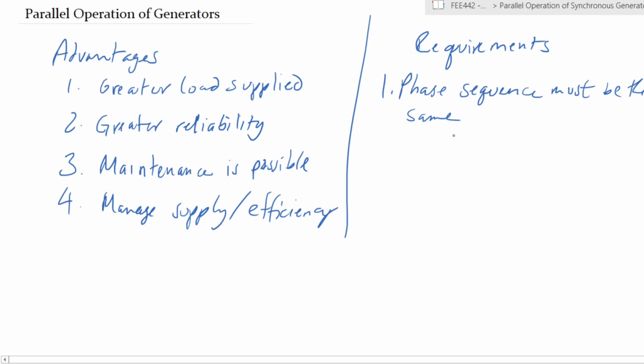Phase sequence means the order in which the red, yellow, and blue phases reach their peaks must be the same for the system that you're connecting to and for the generator that you wish to connect to that system. They must be running in the same order. So if your system that you're connecting to is red, yellow, blue, your generator that is coming in needs to also be red, yellow, blue. If it is opposite, there will be currents flowing between the generator and the system instead of going directly to the load.